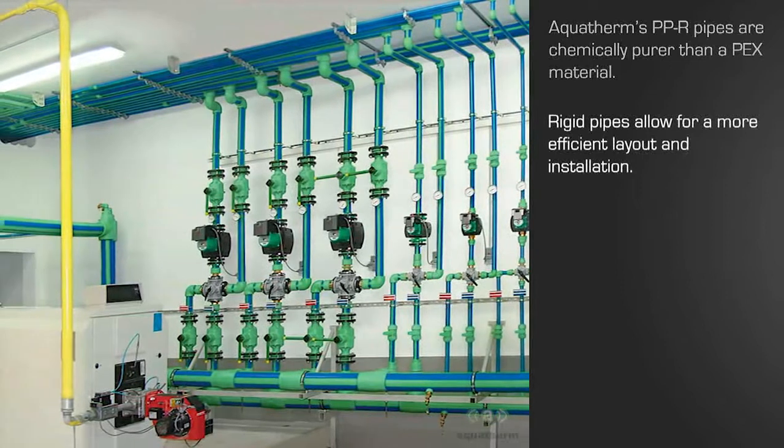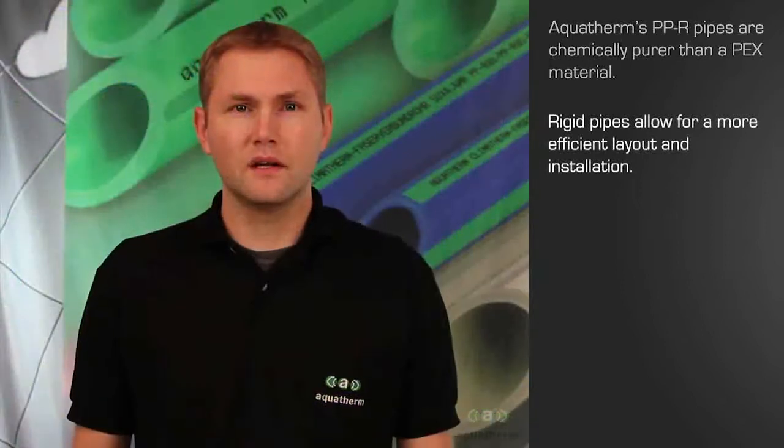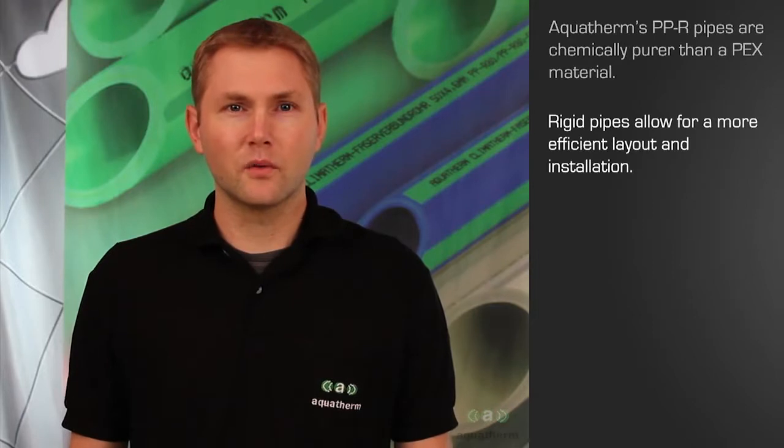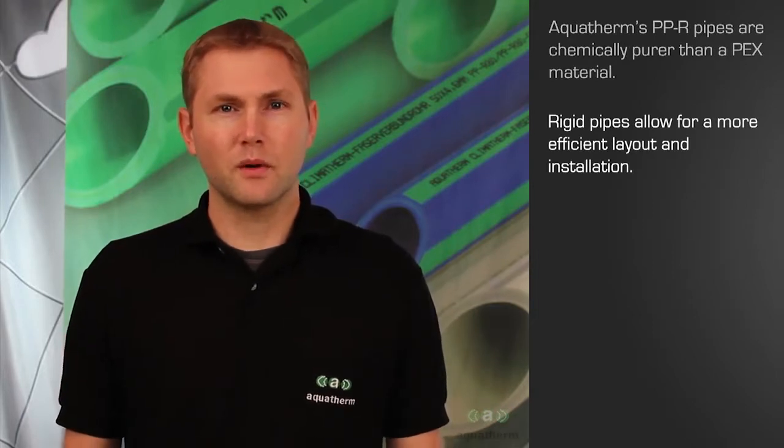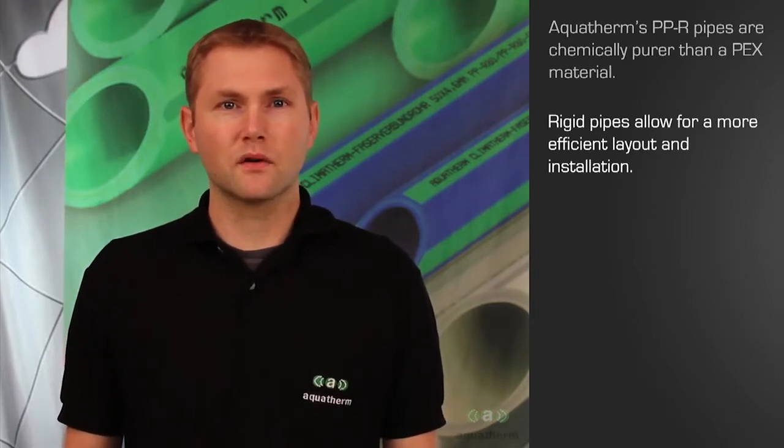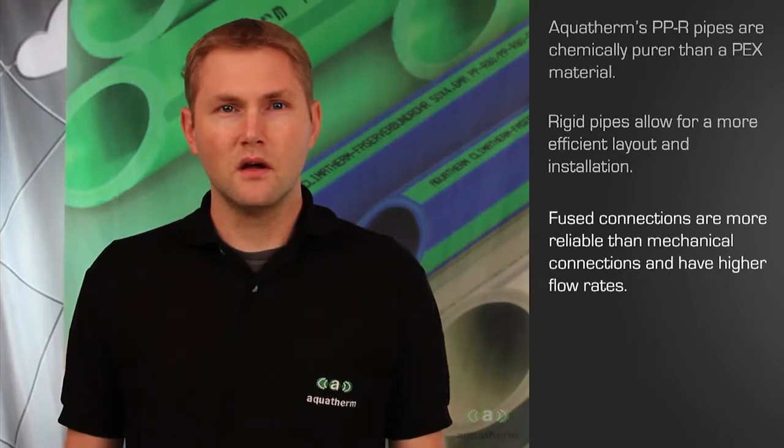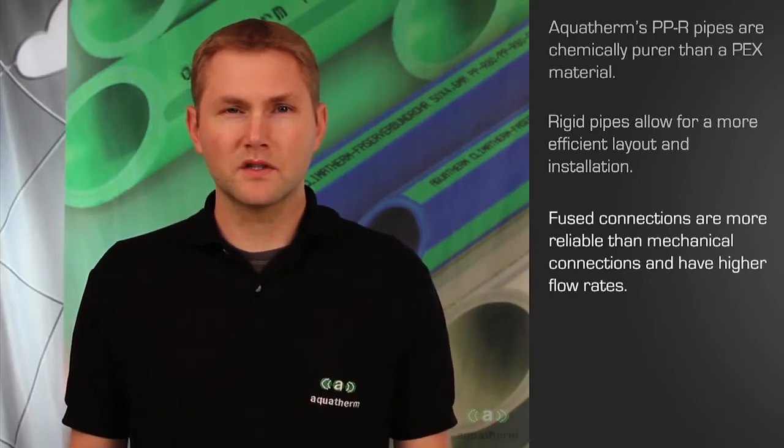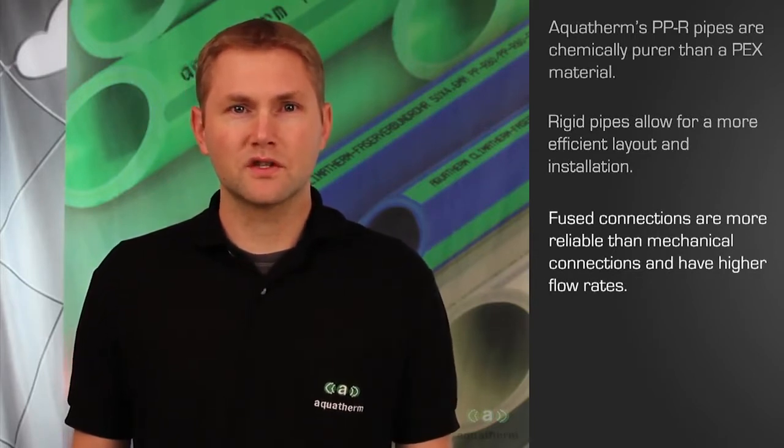Polypropylene also requires fewer supports. The other advantage deals with the connections and the flow rates. Rather than being crimped, polypropylene pipes are heat-fused for a more reliable connection. Polypropylene pipes have a much higher flow rate than PEX pipes with traditional crimped connections.